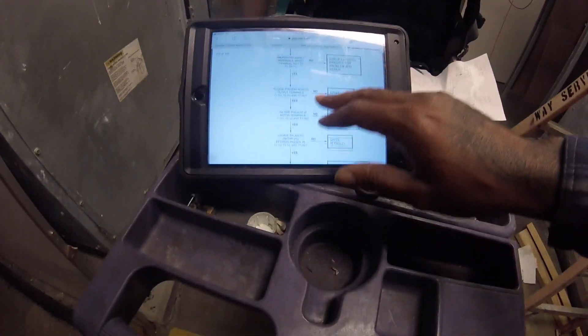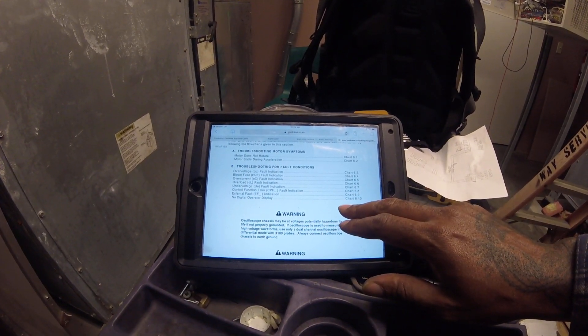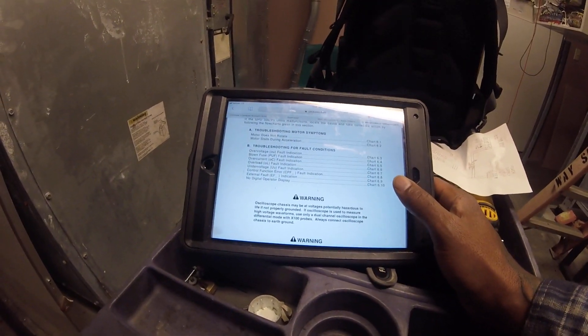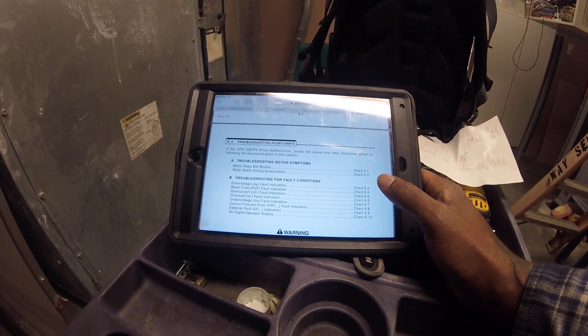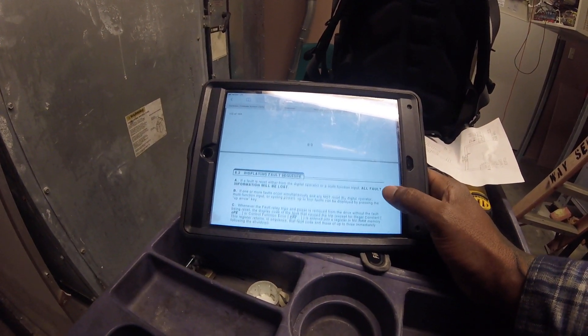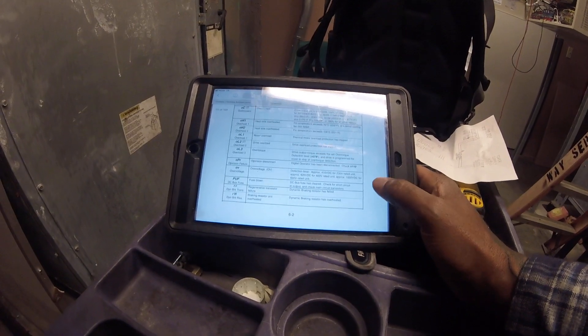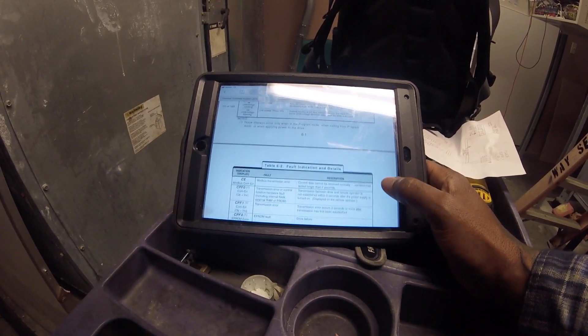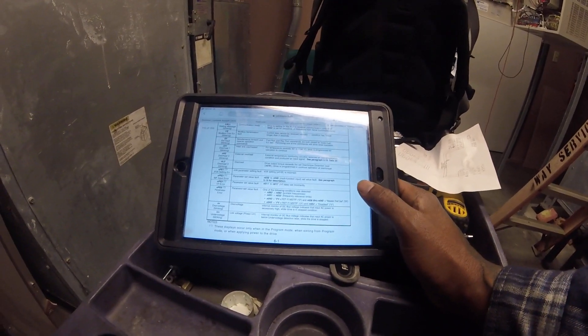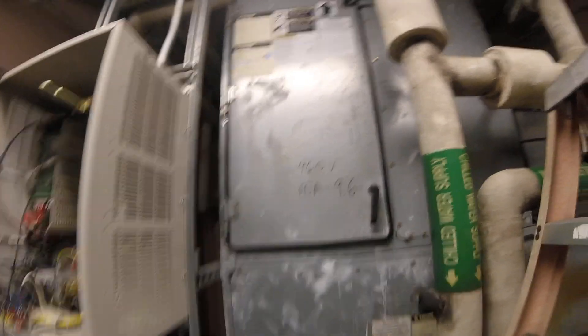I got here at like 7 in the morning and it's 10:26 right now, so I could be all day troubleshooting this unit. They called me out to verify what it was — the other technician says it's the motor. Not trying to override them, but I'm not too sure about that. I checked the insulation and didn't detect a ground. He was on the phone with tech support, and like I said, these VFDs detect any little thing in the motor. I want to try the belts first before we go to replace anything.